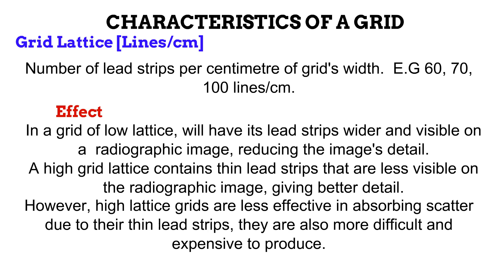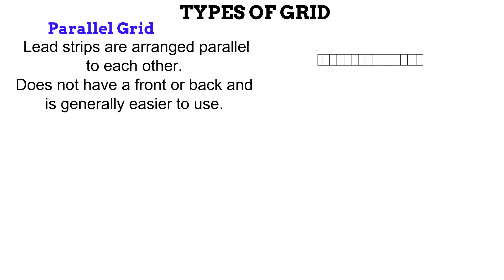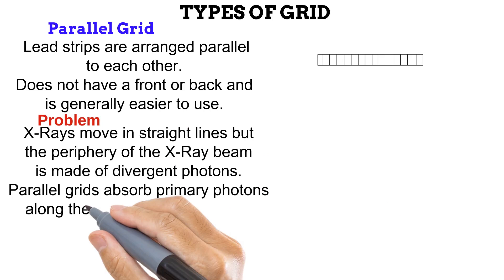Now let us look at the types of grids. The first is the parallel grid. In this configuration, the lead strips are arranged side by side, parallel to each other. Because of this arrangement, this type of grid does not have a front or back — either side can be placed on the image receptor, making it much easier to use, as an upside-down placement error cannot occur. However, the parallel grid tends to absorb some primary photons — the ones at the peripheral edges of the X-ray beam.